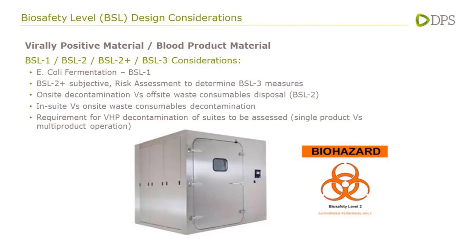Facility design is largely driven by companies' own internal standards being higher than the minimum regulatory standard, bringing it typically to BSL-2 or BSL-2 plus. BSL-2 plus is somewhat subjective — it is largely BSL-2 at large scale with a risk assessment to determine what BSL-3 measures need to be incorporated. For example, for a multi-product facility, BSL-2 does not require VHP decontamination of areas, but VHP decontamination may be implemented — especially in a CDMO — as an example of a BSL-3 measure implemented as part of a BSL-2 plus strategy.